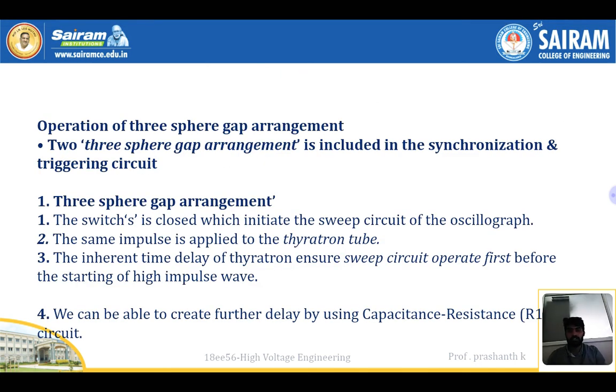Operation of the 3-sphere gap arrangement. The 3 sphere gap arrangement is included for the synchronization of the triggering circuit. The 3 sphere gap arrangement, when one switch is closed, initiates the sweep circuit of the oscillograph. The same impulse is applied to the thyratron tube. Because of its inherent time delay, the thyratron ensures the sweep circuit operates first, before the starting of the high impulse wave. We can create a further delay by using capacitance and resistance R1 in the circuit.